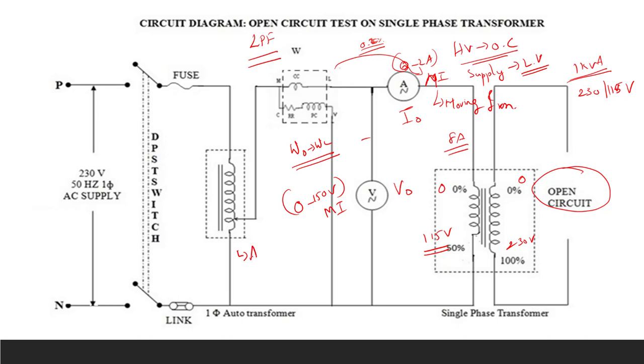By using this autotransformer we are going to set the rated voltage, and the rated voltage will be measured by the corresponding voltmeter V0. After setting the rated voltage, we are going to measure the corresponding core loss as well as the no-load current of the transformer. The fuse rating will be around 120 percent of the rated current — 5 amps is enough for open circuit.